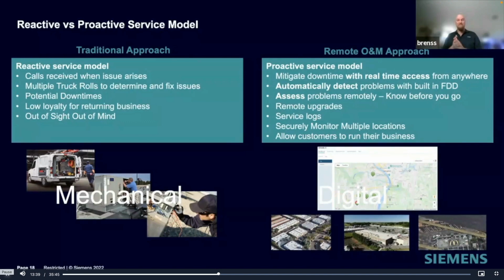But now with the proactive service model, there's hardly any downtime because we have real access from anywhere to our units, automatically detecting a problem with fault detection. Everybody or anybody you choose to get an alarm will get an alarm. We have access to this system remotely from anywhere, so we know before you go what the problem is, and you could bring the part with you. Remote upgrades. We no longer need to roll a truck to plug into a controller to upgrade for new features, new firmware. All that is done from a distance with a push of a button or a schedule that could be done anywhere in the world, and we could do 1,000 units at one time. You could securely monitor multiple locations, and this allows customers to run their business.